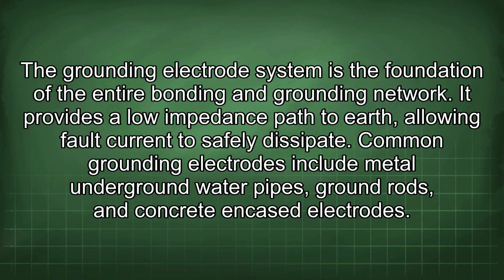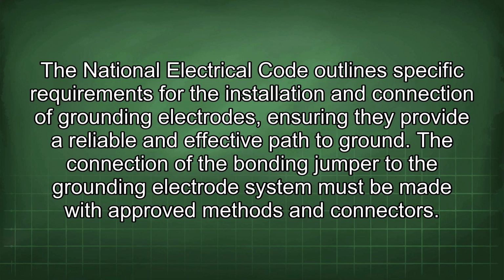The grounding electrode system is the foundation of the entire bonding and grounding network. It provides a low impedance path to earth, allowing fault current to safely dissipate. Common grounding electrodes include metal underground water pipes, ground rods, and concrete encased electrodes. The National Electrical Code outlines specific requirements for the installation and connection of grounding electrodes, ensuring they provide a reliable and effective path to ground.